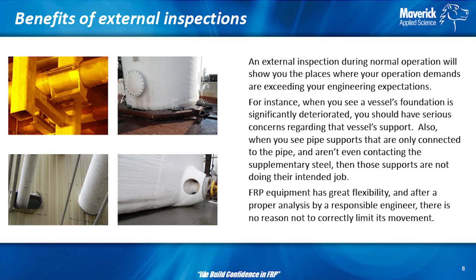When you're doing external inspections, it's not always just the equipment you want to look at — you want to look around the equipment too. For instance, you'd want to see if you're leaking sulfuric acid out of your tank and it's eating your foundation apart, because eventually that tank's going to fail if it doesn't have a foundation anymore. But sometimes everything's perfect, and you want to know that too — that you don't have leaks, that a new pipe or valve you put in looks like it's going great.